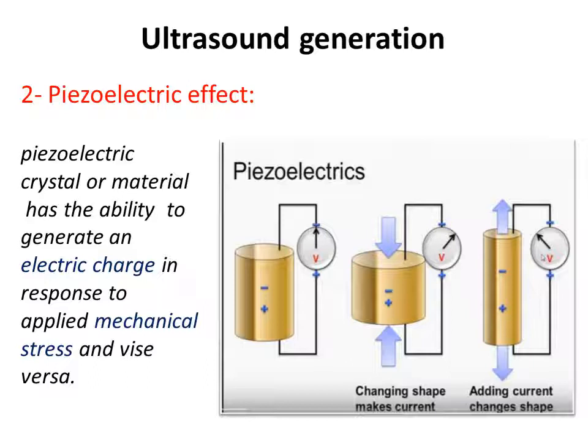How does the ultrasound device generate an ultrasound beam? The device generates it through the piezoelectric crystal inside the transducer. This crystal has the ability to generate an electric charge in response to applied mechanical stress, and vice versa — it converts one form of energy to another. When we apply an electrical charge to the crystal, it converts this electrical charge into an ultrasound beam. When the reflected ultrasound beam returns to the crystal, the crystal converts it back into an electrical charge that carries all information from the body.